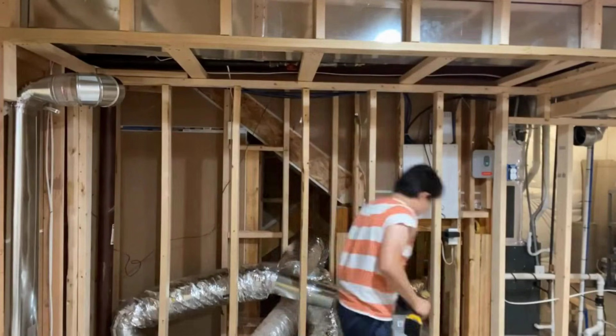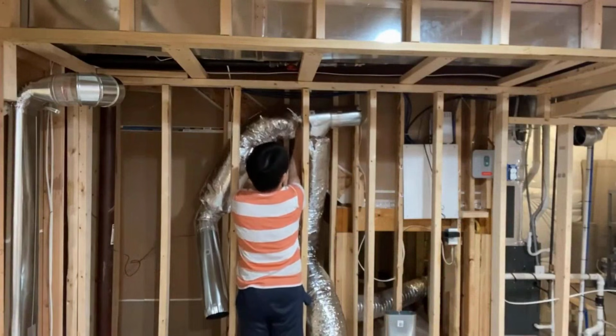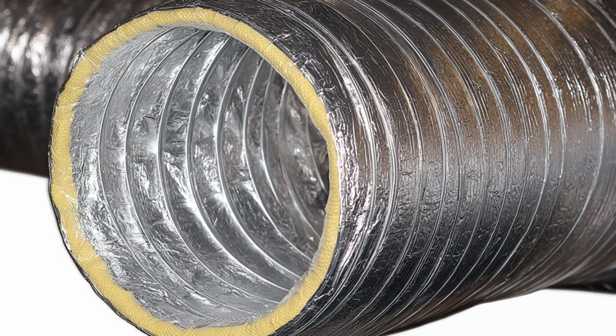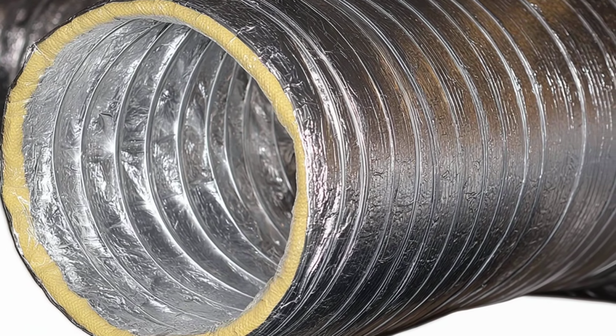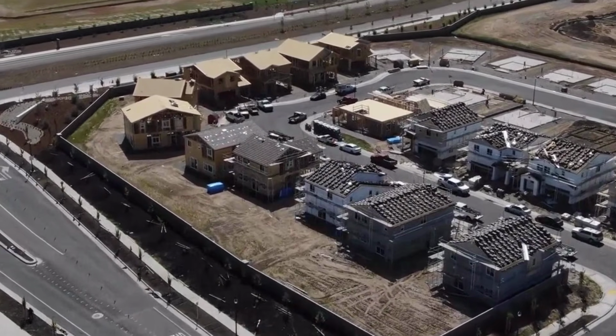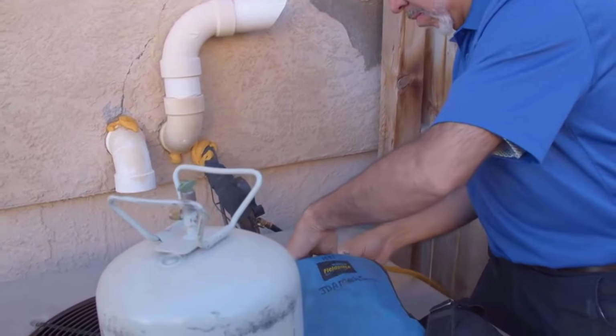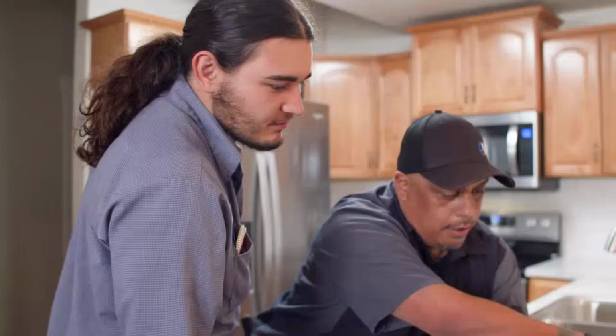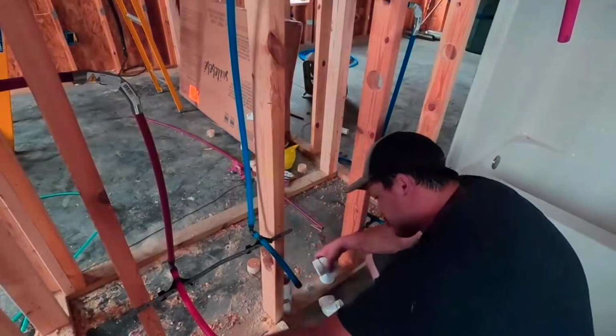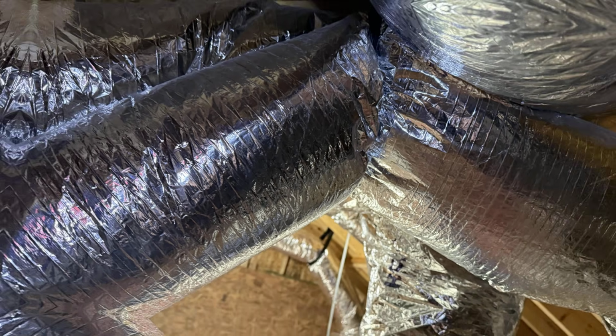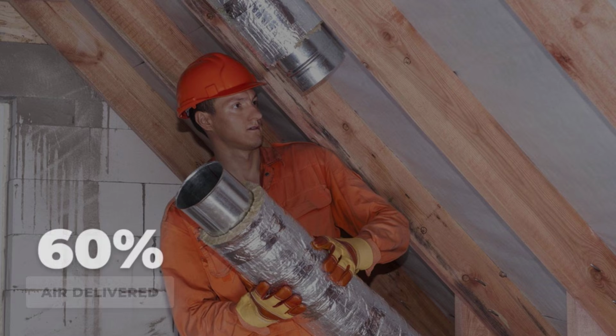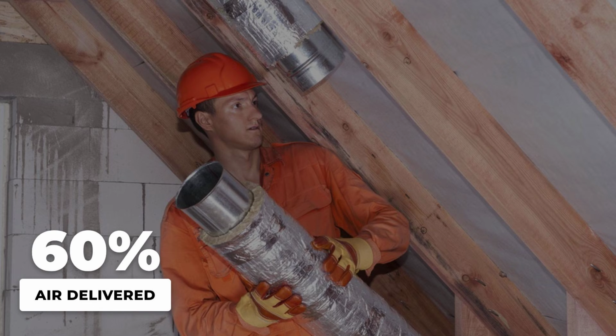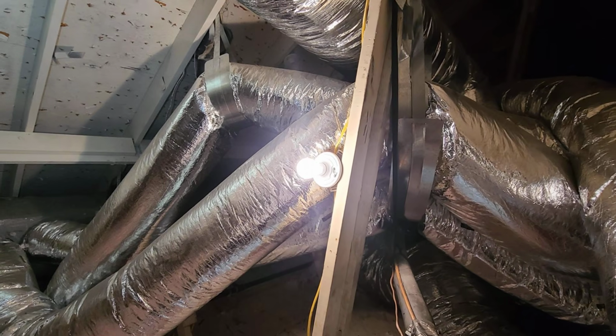The single biggest engineering shortcut in residential HVAC. Flex duct is corrugated plastic, cheap and fast to install. In volume-built homes, it is the default. The problem is, it is almost never installed correctly. Builders pay HVAC subcontractors per house, not per hour. Same piece rate system as builder-grade plumbing, so the duct gets snaked through attics with sharp bends, kinks, and excessive slack. One documented case involved a 19-foot run left with over 40 feet of unstretched duct.